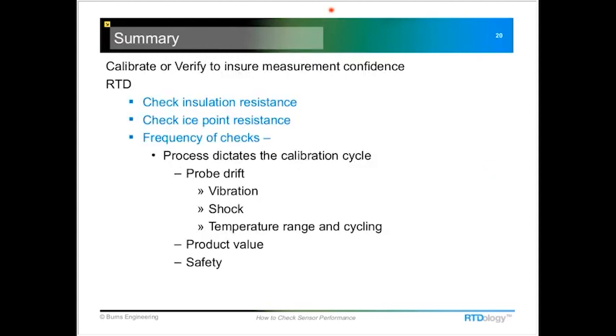Kind of wanted to reiterate here. First off, check the insulation resistance, then do the ice point, and then there's really no hard and fast rule as to how frequently you should be doing these tests. It's really up to your own level of confidence in that point, and it might be a safety issue, product value, and the characteristics of the process, what it's doing, vibration, shock, those kinds of things. They are all going to affect the long-term accuracy of that temperature probe.